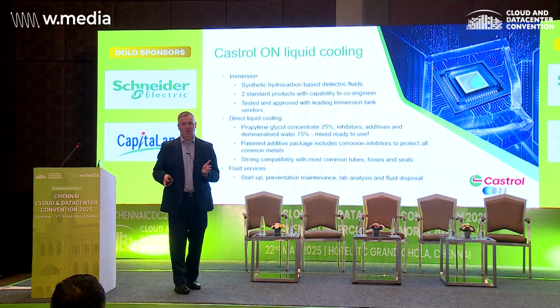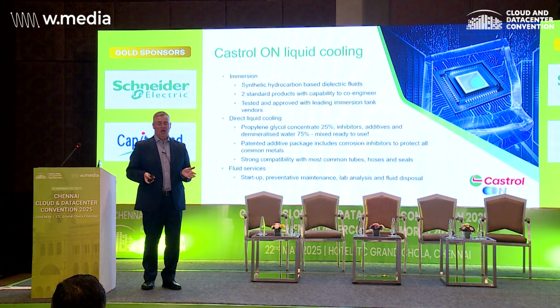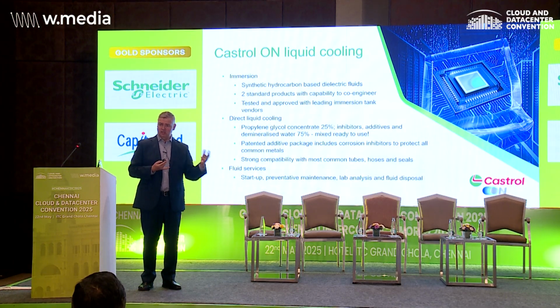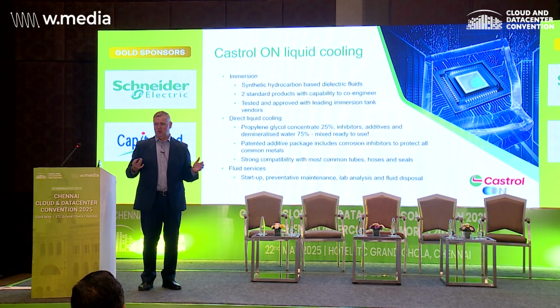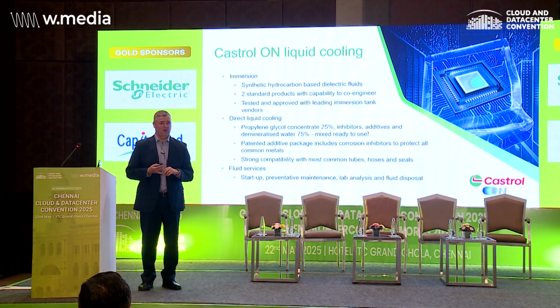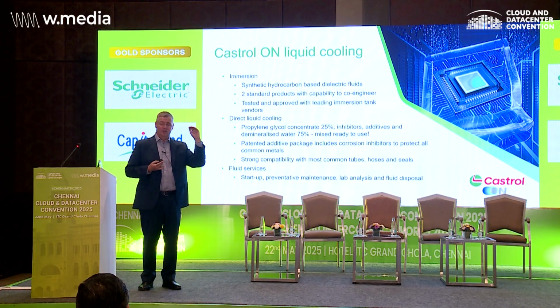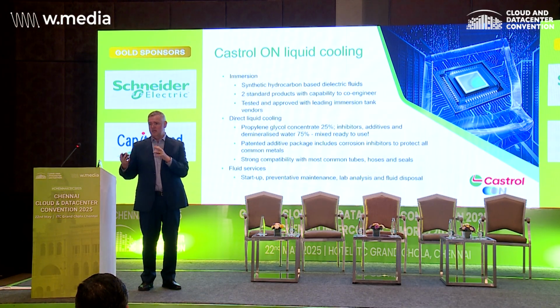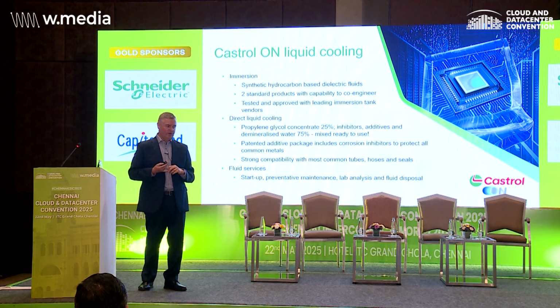So obviously as a large oil company, we started in immersion. We've got a couple of products within that portfolio. When talking immersion, you've got two basic levers: viscosity and flash point. The lower the viscosity, the higher the heat transfer, and the lower the pump power as well. So that's one lever, but it impacts flash point, which is where the fumes can potentially catch fire above a certain temperature. So depending on the jurisdiction, you may need to engage with your different fire authorities on that.